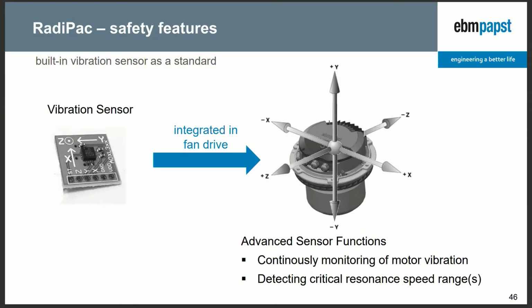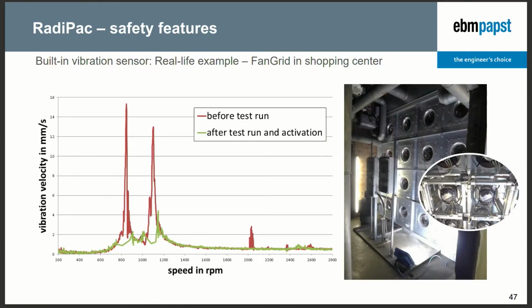Vibration sensor, which is now included in our RadiPac range, starting from 4 kilowatt. It's a sensor on the PCB that measures the vibration velocity in millimeters per second. So how is it activated? When operating the fan the first time, you switch it on and ramp it up from 0 RPM to maximum RPM, and the fan runs through the whole range. And you know, every rotating system has certain natural frequencies where you have a peak. So during the test run, the fan learns.